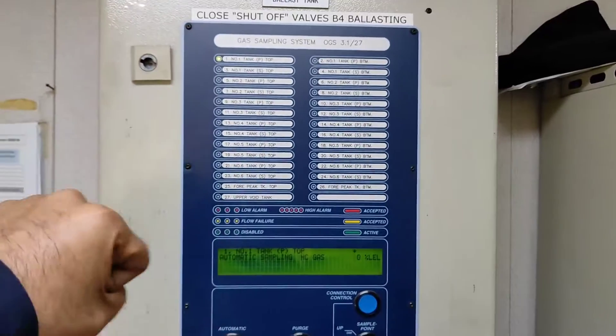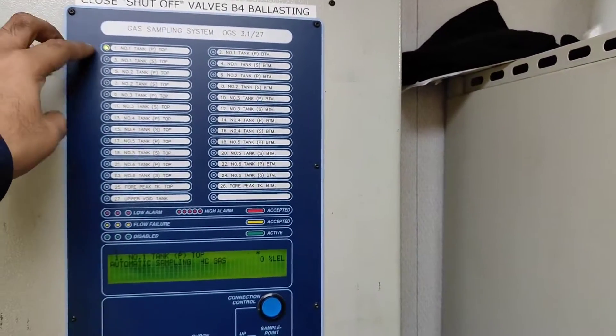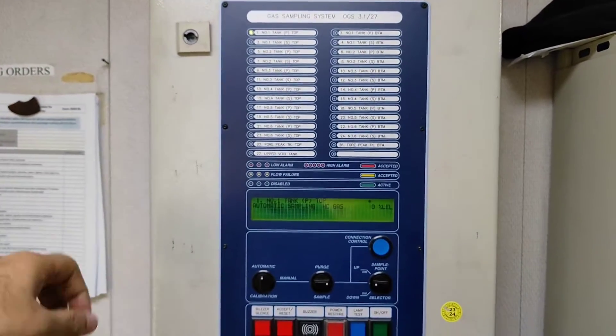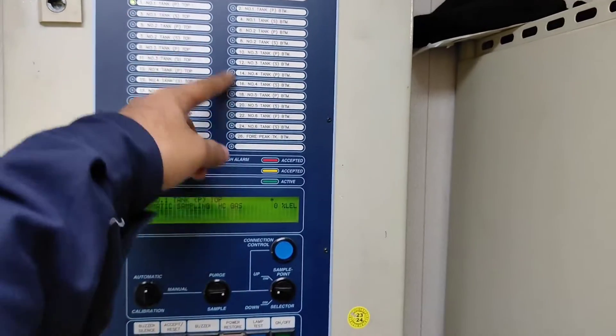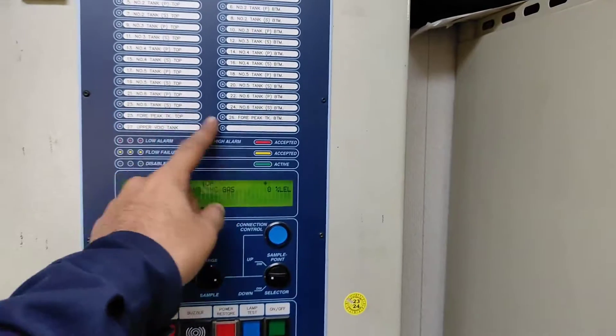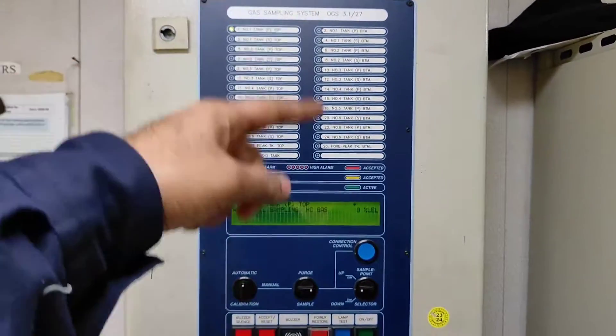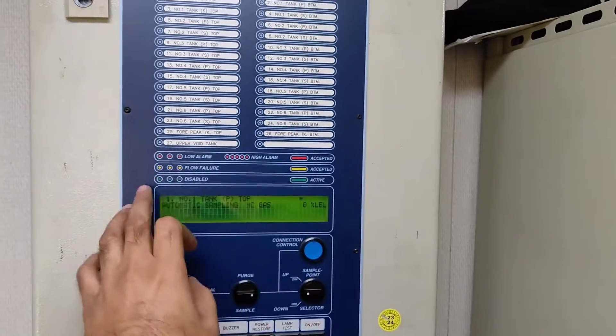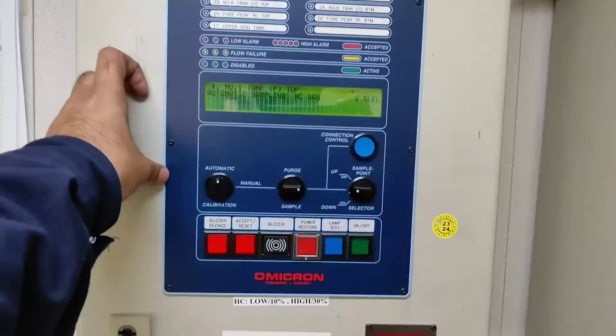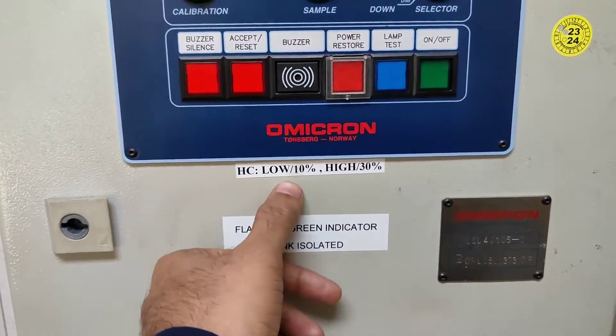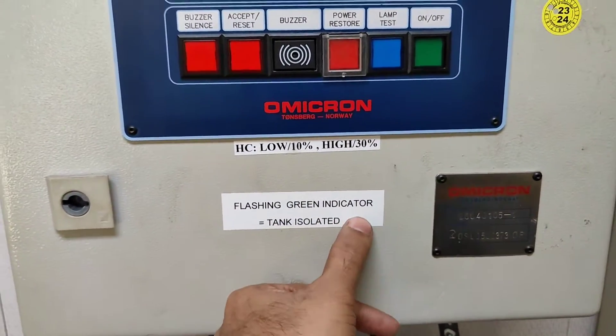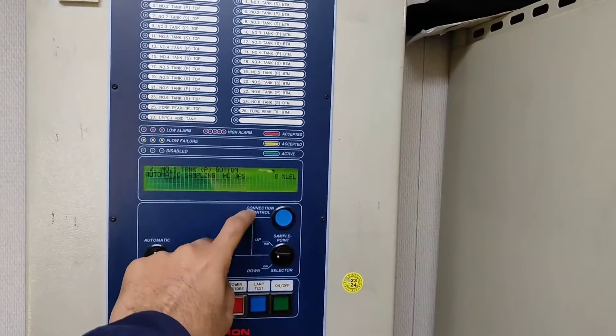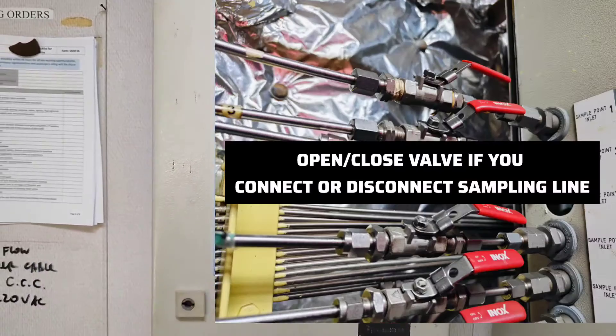In automatic mode, the system will first purge all the sampling lines. For example, if it has selected number one, it will push that line and after one minute of purging it will take a sample. It goes through all tanks — one, two, three, four — and after 27 it repeats back to number one. High alarm is indicated as such, flow failure is yellow, and disabled has its own indicator. HC low is at 10%, high is at 30%. A flashing green indicator means the tank is isolated. If all are connected, none will be flashing.